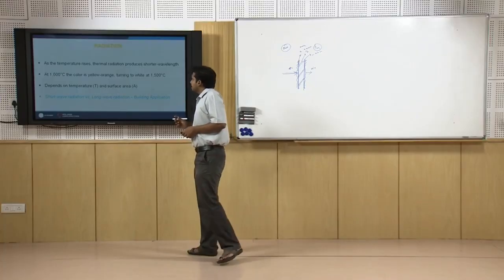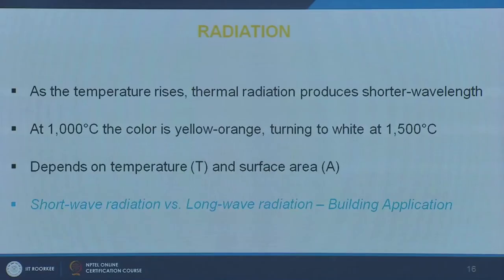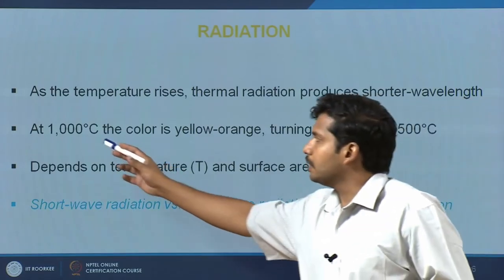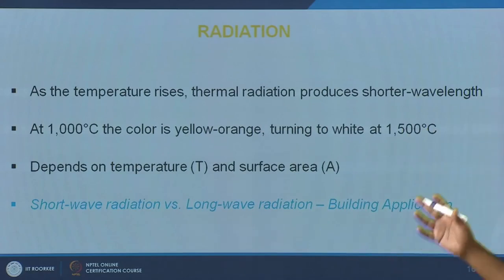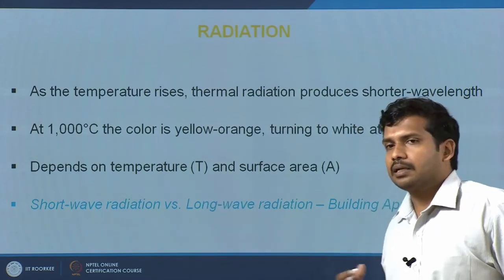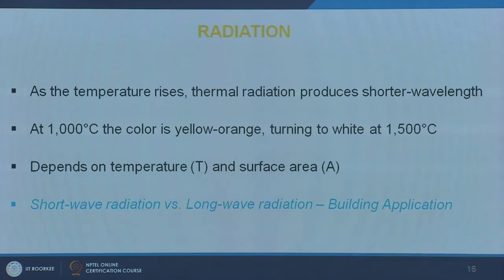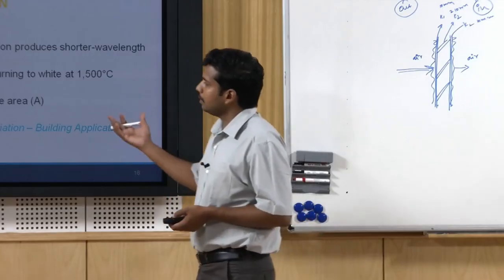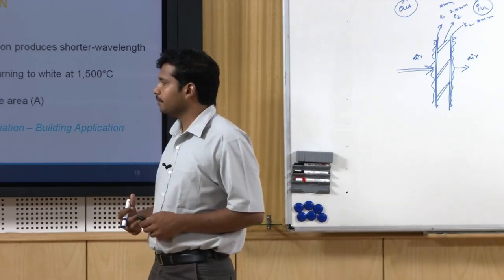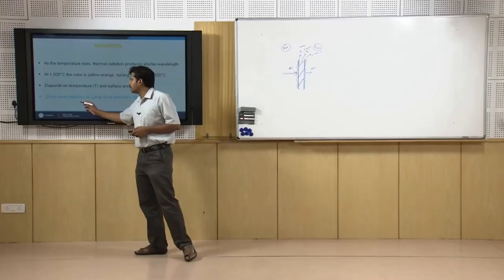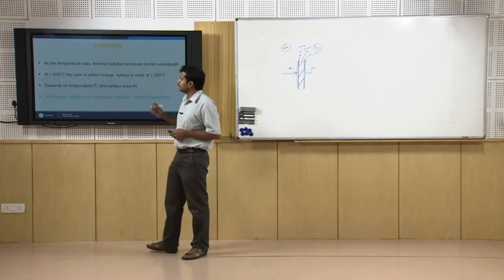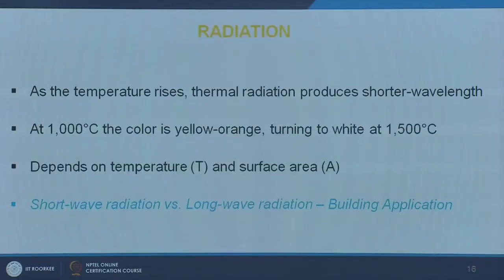As the temperature rises, the thermal radiation produces more short wavelength radiation. Say, for example, at 1000 degrees centigrade the color of light will be yellow orange, and it would turn white as the emitting surface increases in temperature. We should remember the heat transfer depends on the temperature of the emitting surface and the surface area which is receiving it. There are two types we are interested in for building applications: short wave infrared and long wave infrared.